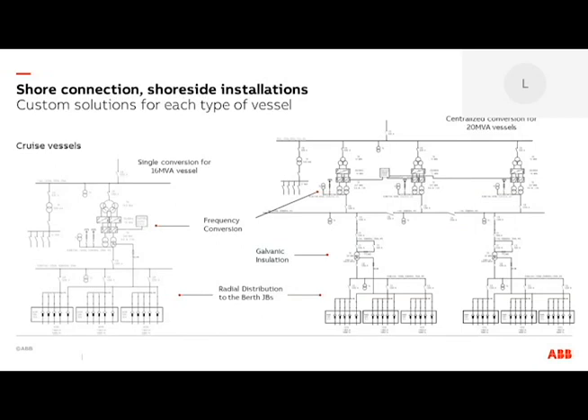Here we can see different types of solutions. One is for a single vessel: one large frequency converter capable of delivering up to 16 MVA, considered the minimum necessary for a cruise vessel, with a different connection point on the berth, since there is no standard position for the connection panel on board the vessel.